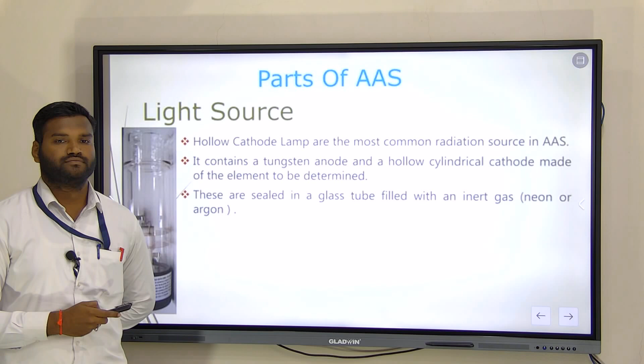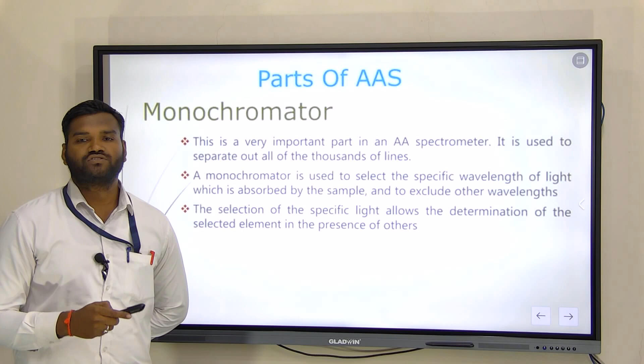Next, that is the monochromator. This is a very important part of the atomic absorption spectrometer. It is used to separate out all of the thousands of lines. A monochromator is used to select the specific wavelength of light which is absorbed by the sample and to exclude other wavelengths. The selection of the specific light allows the determination of the selected element in the presence of others.